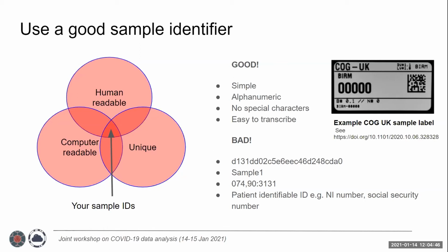So using this particular ID, you need that ID to be easy to read by a human and a computer, and you need that ID to be unique. And I will tell you from experience that it is immensely difficult to change the ID from one format to another halfway through a project. So I recommend that you come up with a good naming scheme and use that throughout.